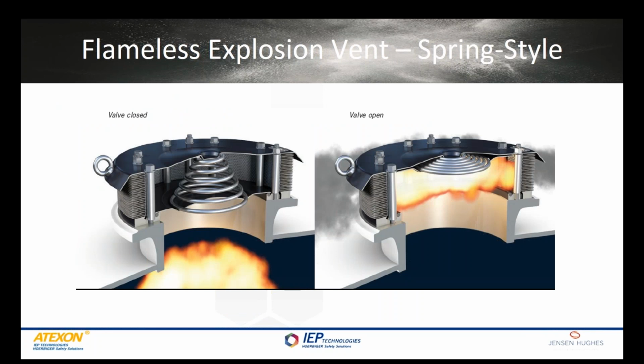And here's just a graphic showing a spring-loaded style flameless vent. The picture on the left-hand side, you'll see the vent in its closed position. When the pressure from the explosion occurs, it'll push the plate up that's beneath that funnel-shaped spring, and the spring will compress. The flame and the hot dust will be pushed towards the flame arrestor, which will then absorb that heat and safely just release that heat to the outside without any flame. So this is just one alternative to standard explosion vents.